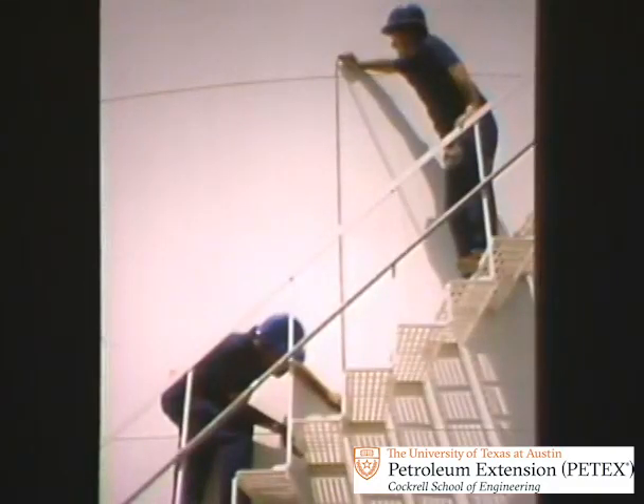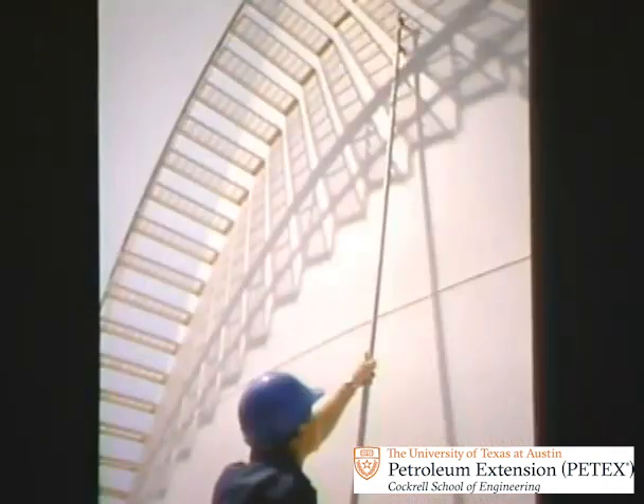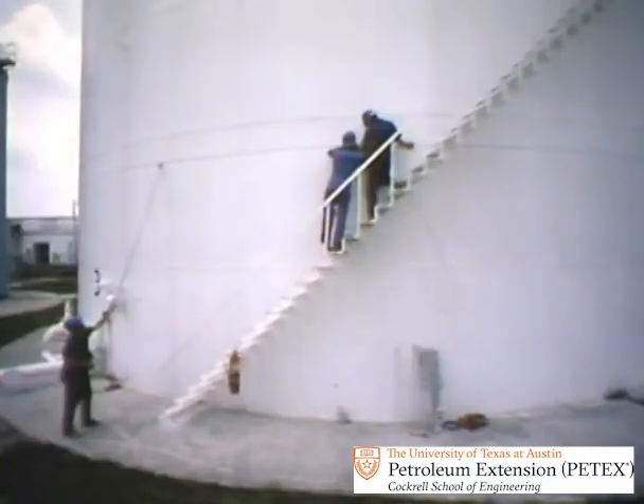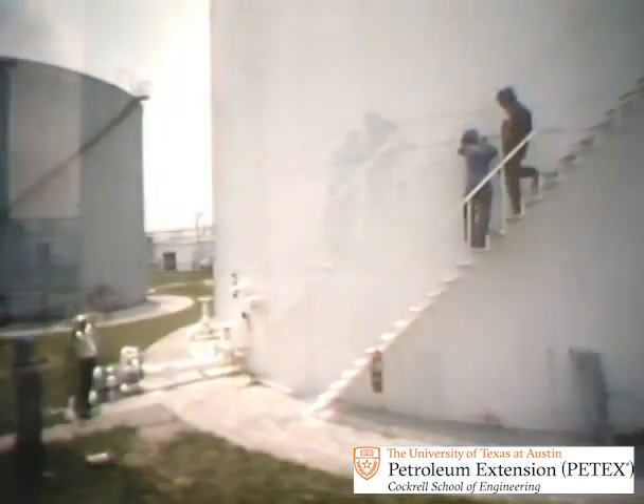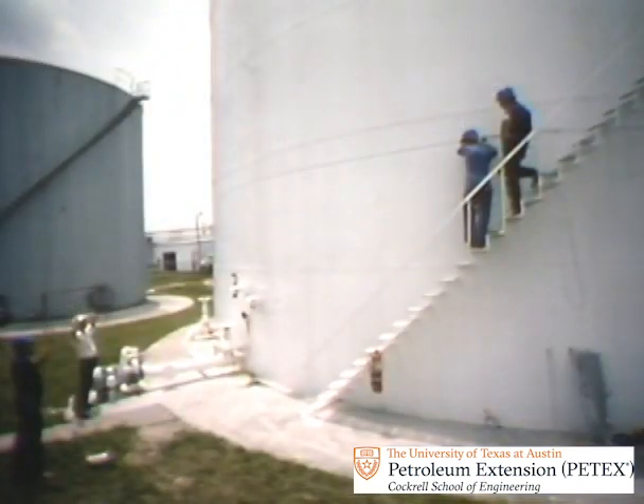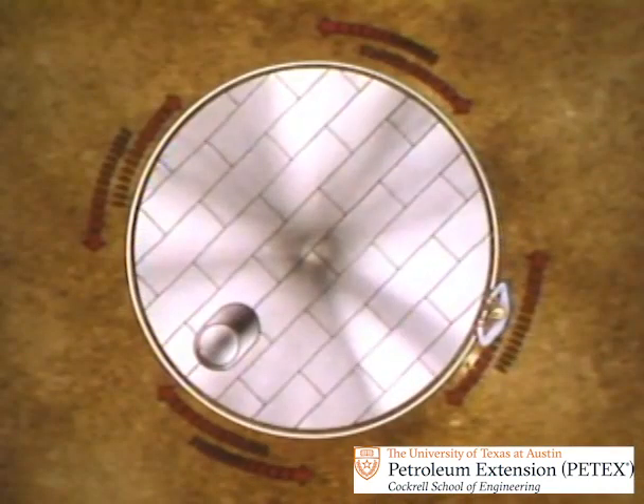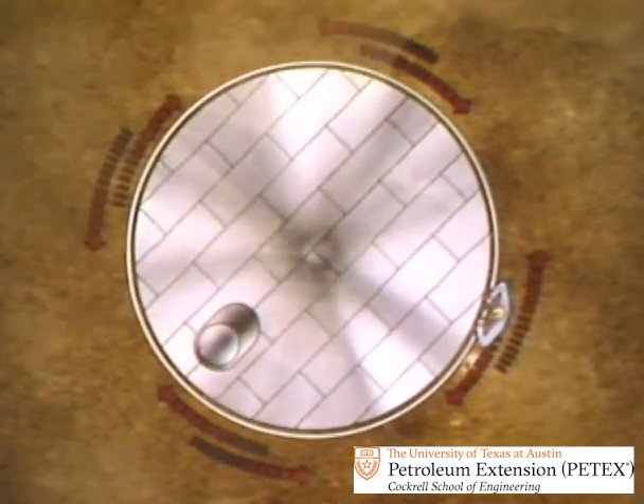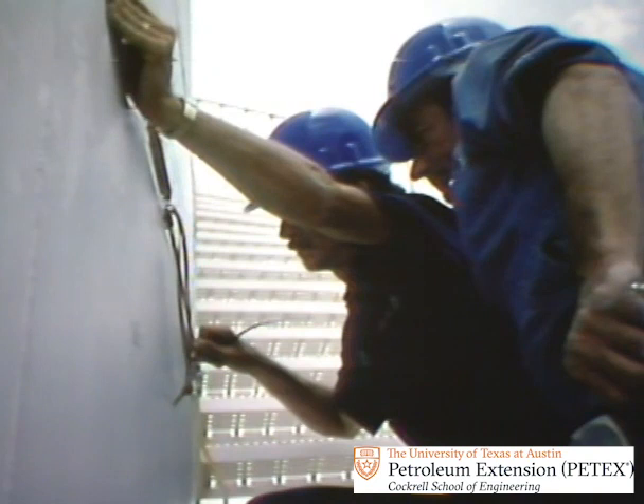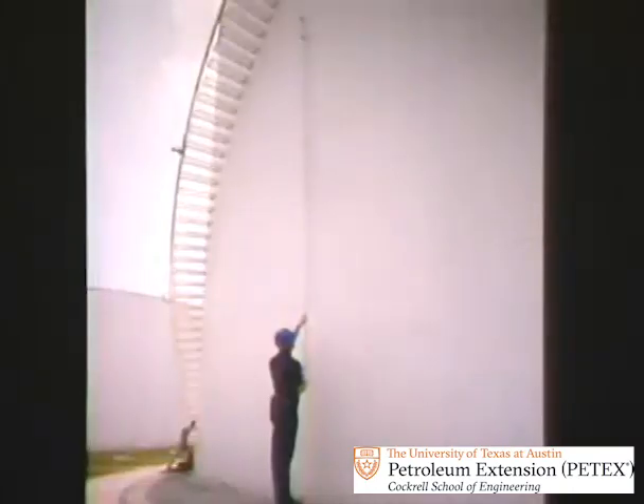To continue the circumference measurements, the crew measures the width of the second ring. To mark the tape path on the second ring, they use an extension on the strapping pole to reach it. They then place the working tape on the path marks and take in tape slack. They check to be sure the tape is on path. They break the frictional resistance, the surface tension, between the tape and shell, and pull the required tension on the working tape and read it. The crew measures the circumference of the next two rings in the same way.